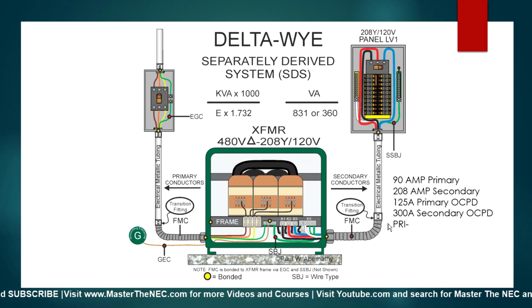Now, it is metal, okay? And this is where I see a lot of misconceptions online. It is metal, so it does have to be bonded. However, here's where some confusion comes in. A lot of times people will loop things through it. They'll loop their supply side bonding jumper through it, or loop their equipment grounding conductor through a bonding bushing, and all those kinds of things. I want to discuss that a little bit because there seems to be a lot of confusion with that, and we're going to dispel that right now.